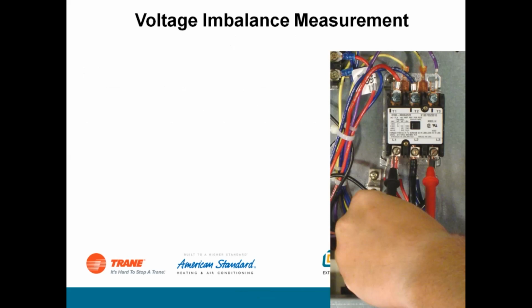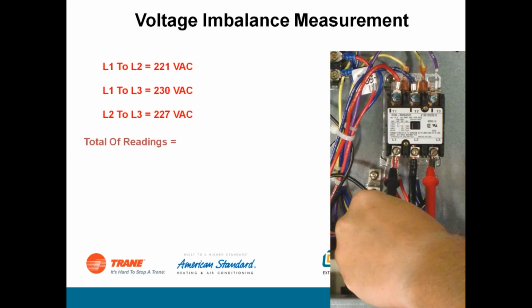On three-phase equipment, we want to make sure we've got a good balance on the voltage. It's important to make sure the power is right, the voltage is right. The way to do that is take some voltage readings, line 1 to line 2, line 2 to line 3, line 1 to line 3. Just make sure we get all three voltages and see where we're at. They should typically be pretty close, usually within a couple of volts of each other. If you see something that's out of whack, like in this example here, you can probably tell right now there's going to be an issue.